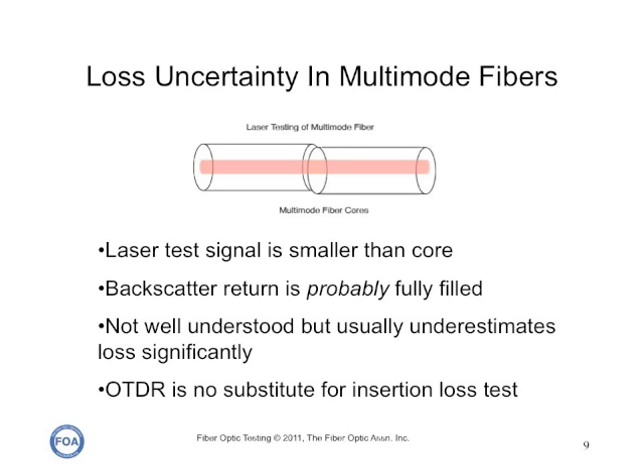OTDRs have other errors associated with measuring multi-mode fibers. The outgoing laser test signal is much smaller than the core, so it tends to underestimate loss. And the backscatter signal is probably fully filled, although this is not well understood. So what you see is an average of the outgoing and the return signal. The OTDR, particularly with multi-mode fibers, is no substitute for a properly done insertion loss test that controls the mode power distribution from the test source.